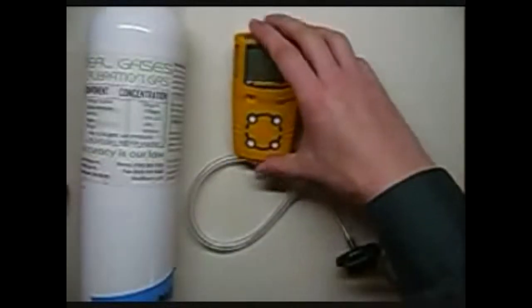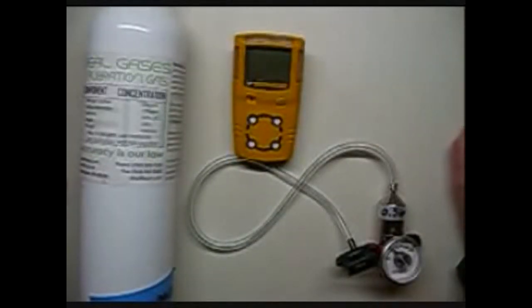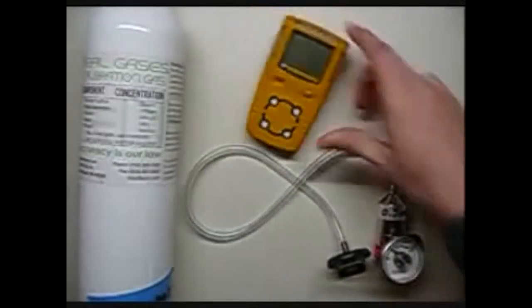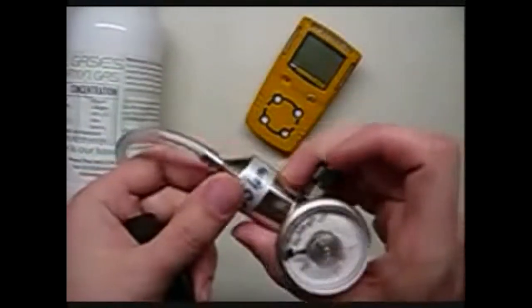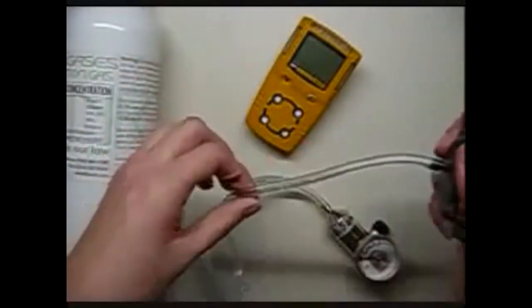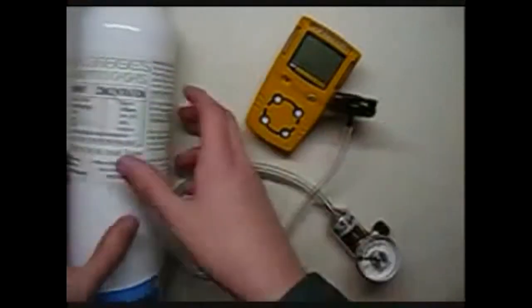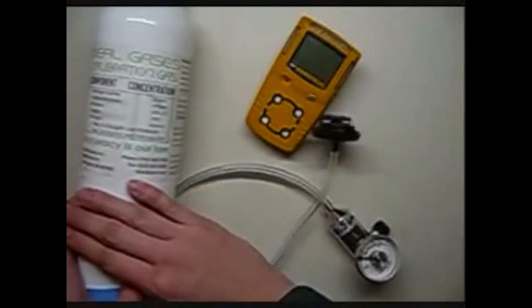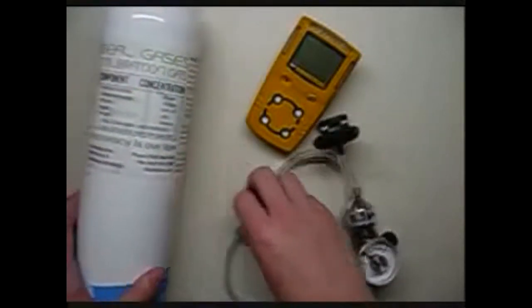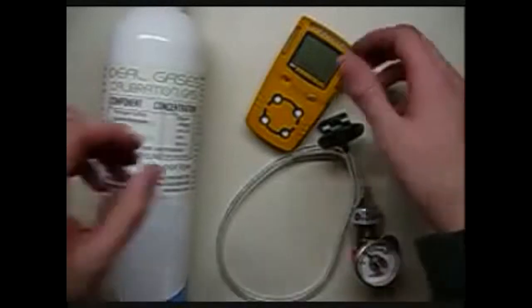What we're going to be working on today is the BW GasAlert MicroClip 4-gas. What you'll need is the monitor itself, a 1.5 liter per minute fixed flow regulator, the calibration cup that comes with it, and the tubing. Also one cylinder of trusted calibration gas. We obviously use nothing but Ideal Gas's brand here.